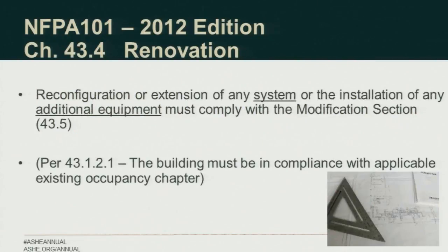So if I reconfigure or extend any system or add any new equipment, that portion of the project may still be a renovation, but that portion has to meet the requirements for modification. Because if you look at the definition of modification, it is extension of a system, addition of a system.